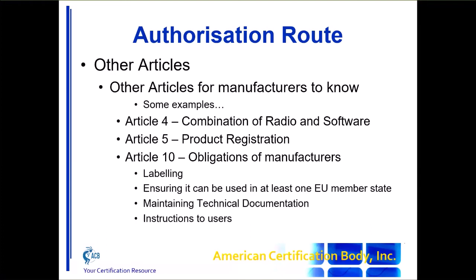Article 10 is important for any manufacturer - it's called obligations of the manufacturers. That covers labeling, the requirement that the manufacturer must check their product can be used in at least one EU member state, what instructions must be provided, and things like that.